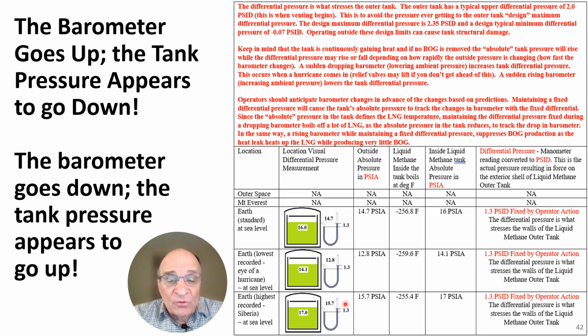Those were all done in order to keep this differential pressure constant. Now here's where I want to point out the saturated temperature and pressure. What is the temperature of your LNG? The temperature of your LNG is dependent upon the pressure that the LNG is stored at. In this particular case, it's 16 psi absolute, for which I use methane as the LNG. It equates to a temperature of minus 256.8 degrees Fahrenheit.